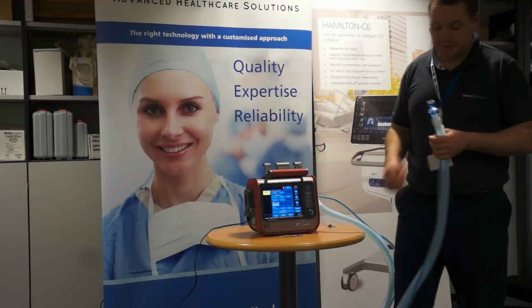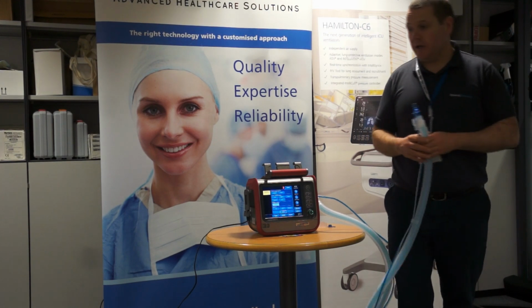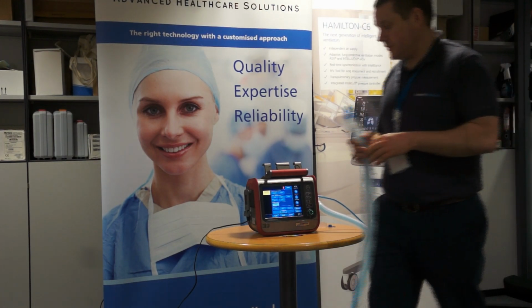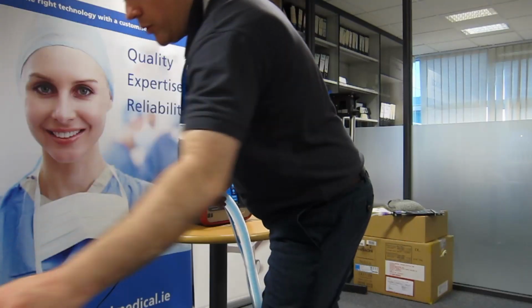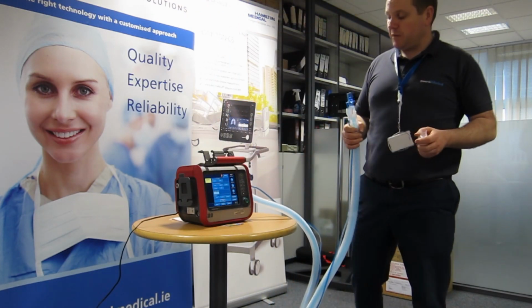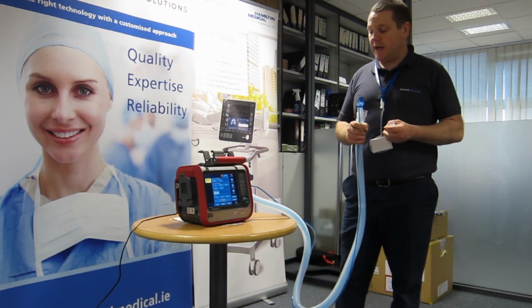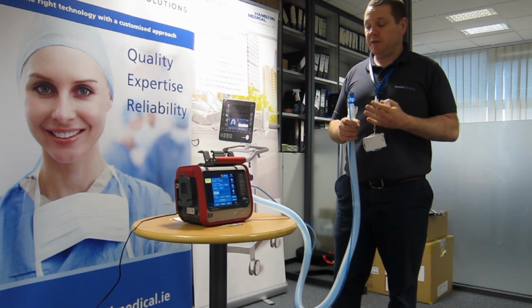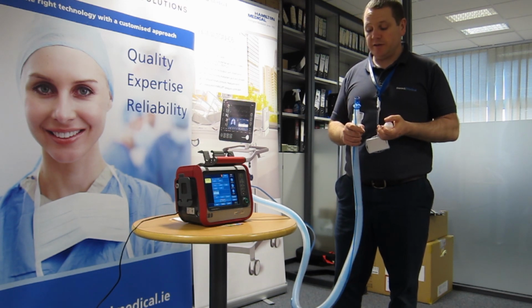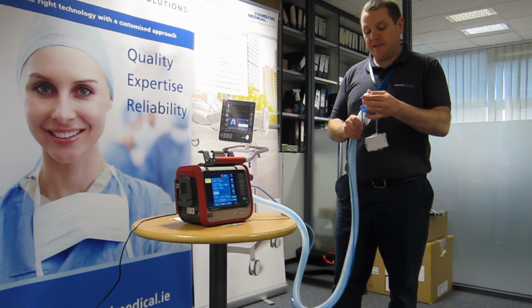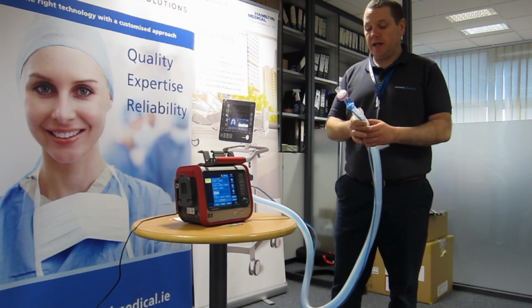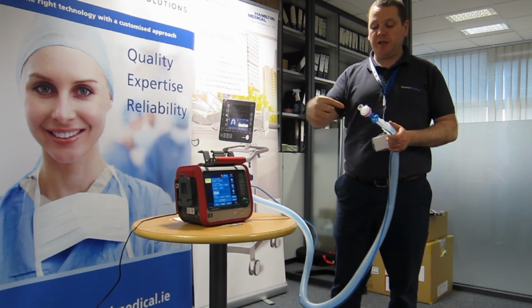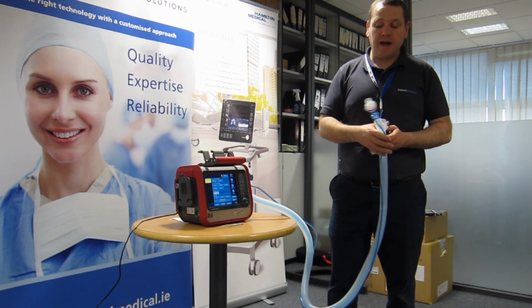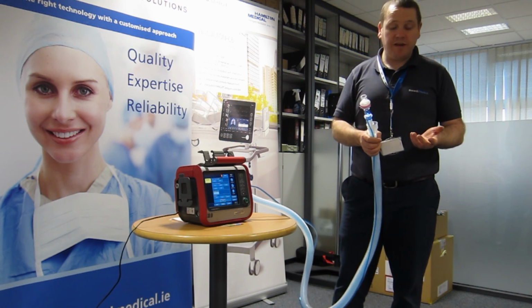ASV is specific to Hamilton, so I'm going to run the ventilator on ASV so we can have a look at that. It's easier to explain. Very important as well, the recommendation for turbine driven ventilators is that you would filter the air that's been generated by the ventilator before it's delivered to the patient. So a HME filter here will suffice, and also here we're filtering going to the patient, but also more importantly we're filtering air coming from the patient. Very important if you have an infectious patient.